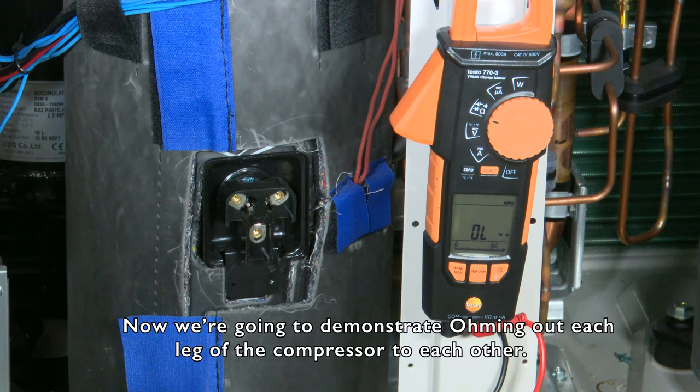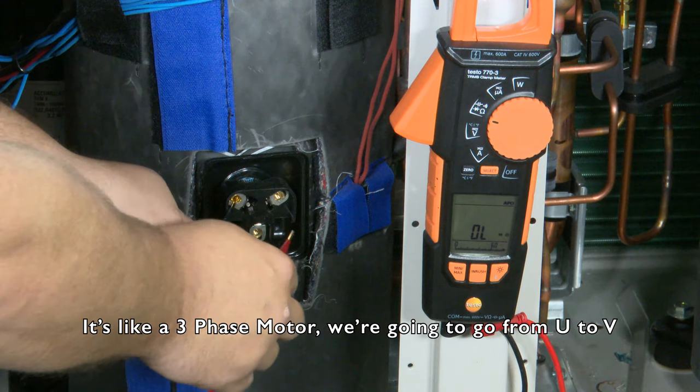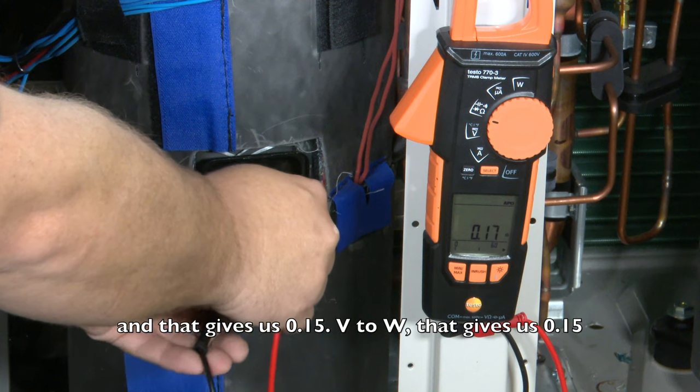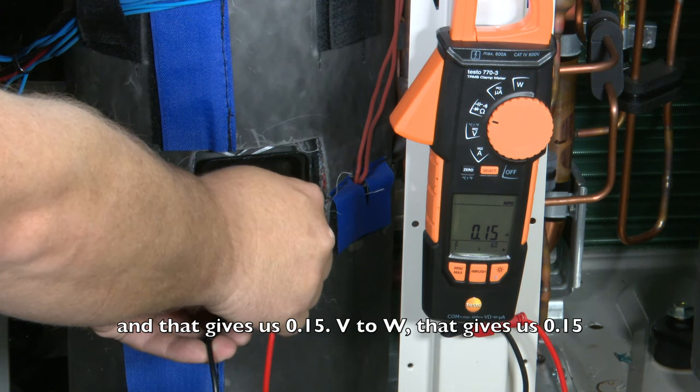We're going to demonstrate ohming out each leg of the compressor to each other. Just like a three-phase motor, we're going to go from U to V — that gives us 0.15. V to W — that gives us 0.15.